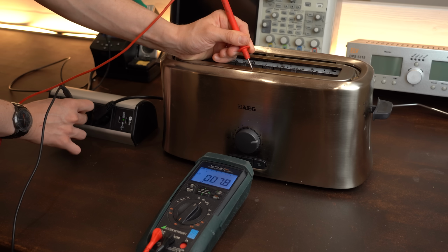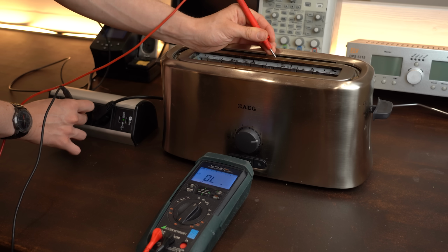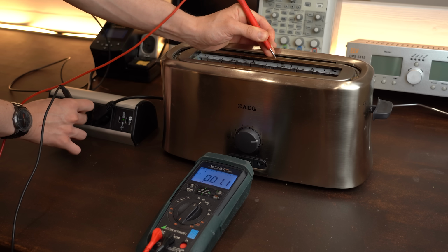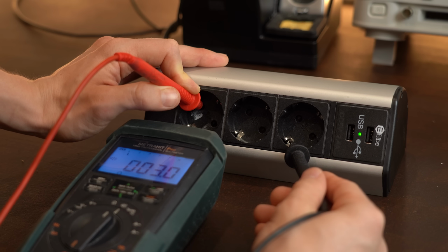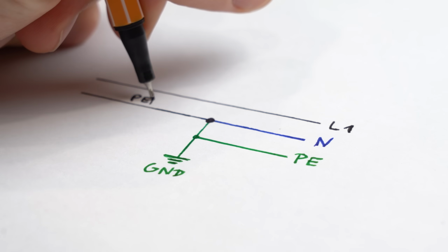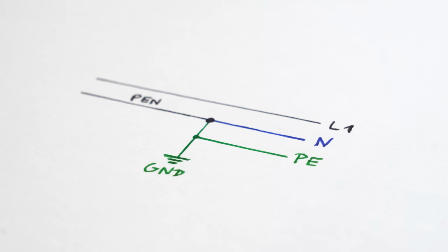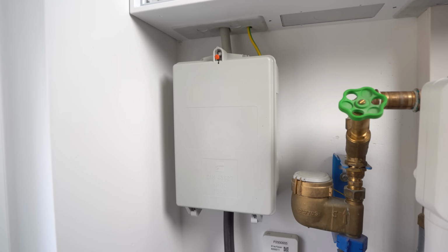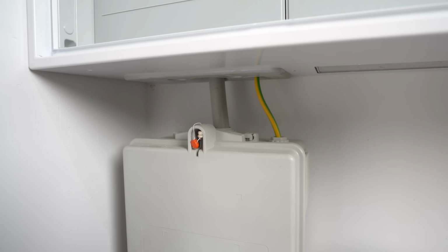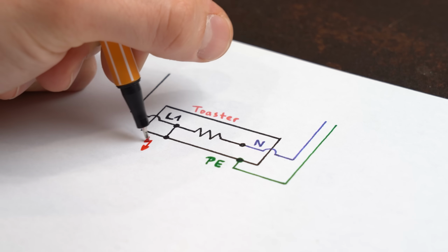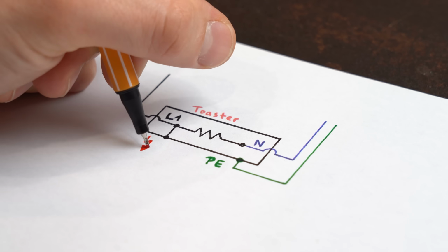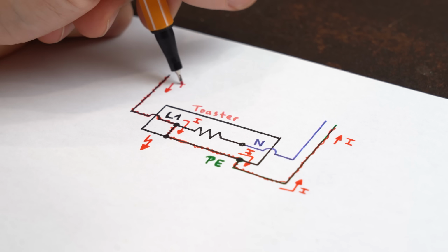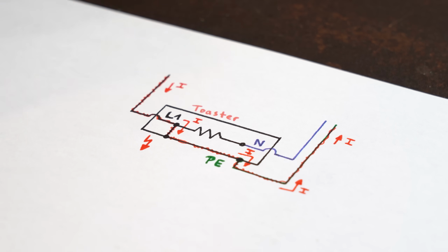To prevent this, the earth wire is not only directly connected to the metal housing, but also to our neutral wire. This connection is done inside or near the main distribution panel, which I can sadly not show you because mine is locked. So as soon as live and earth touch each other, we get a big short circuit current flowing, which is actually a good thing.